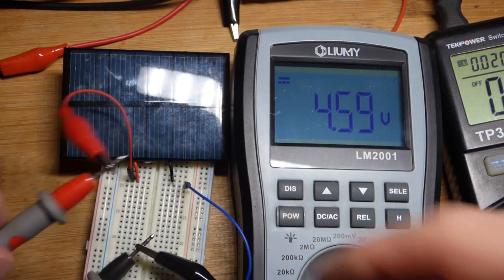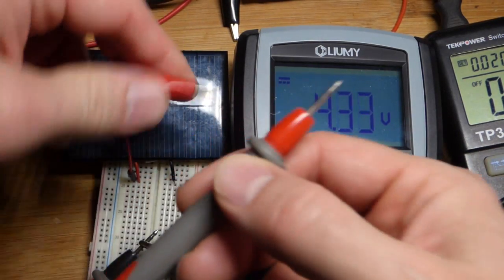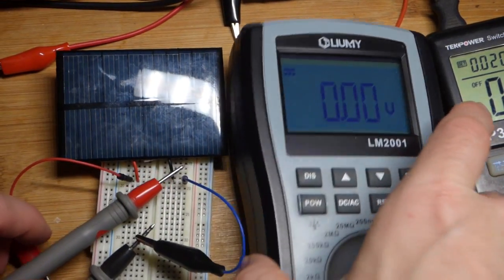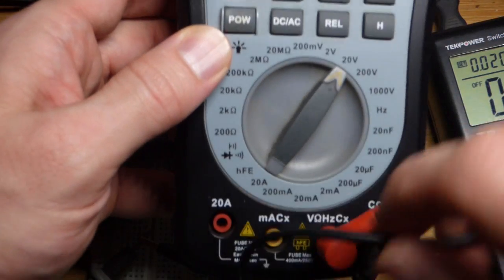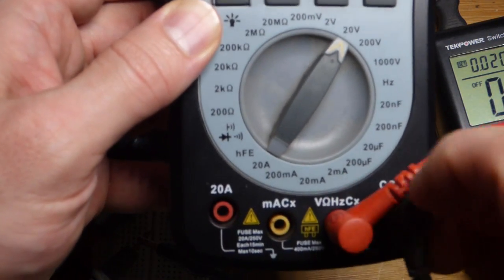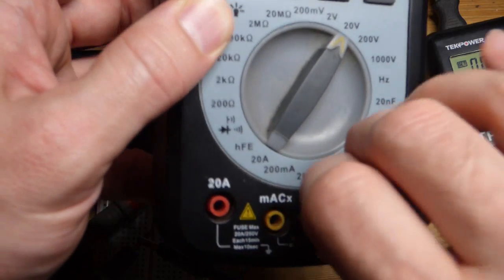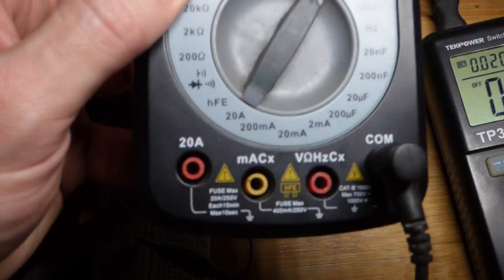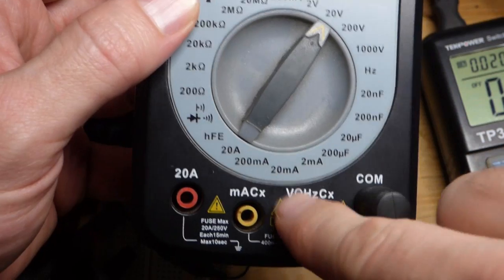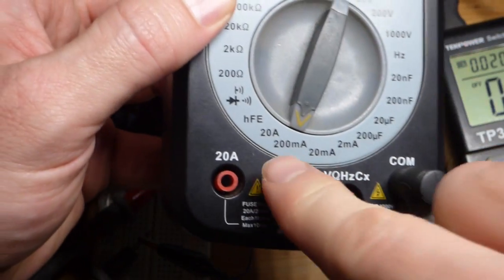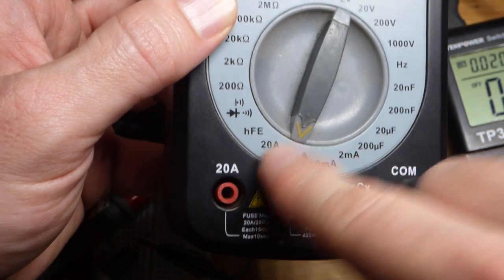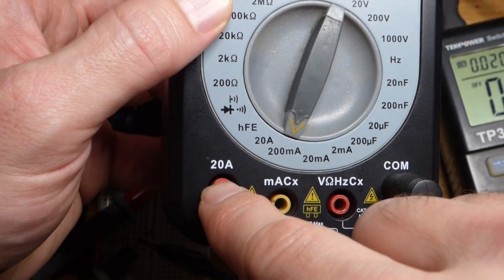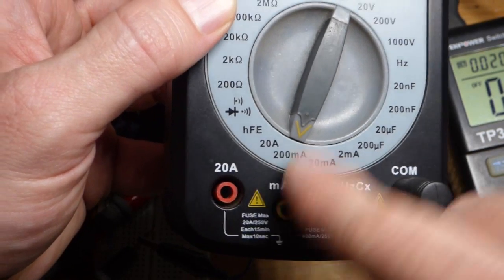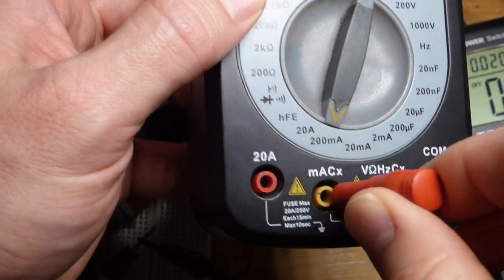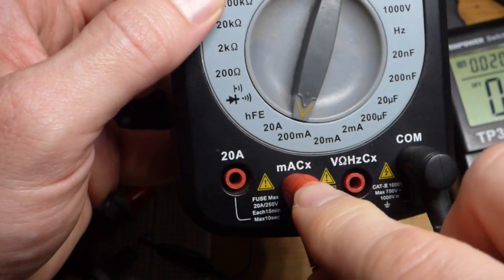So now that brings us to current. We want to unplug the multimeter at this point because we don't want to be running current while we change settings. We are going to move the probe to milliamps, but before we do, I will set it. I already know it's less than 200 milliamps of current that we're going to get, so we can go there. Again, if I wasn't sure, we could go to 20 amps, make sure it's less than 200 milliamps, and then at that point, jump over, work our way down. But here, we're just going to measure milliamps right there.